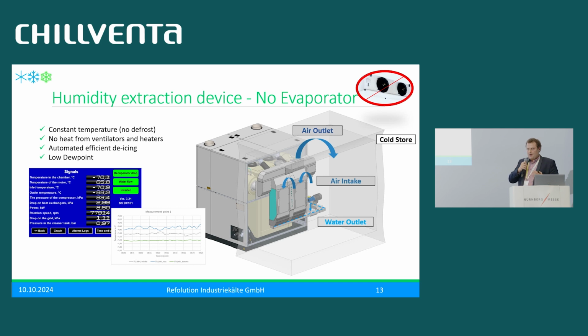And then you ask, but there are ice crystals and at -80 also CO2 crystals, and we have dirt and other things. Yes, and the machine is sucking over 2 filter cartridges. They are obviously redundant, so if one fails, it can suck over the other. And if they are full, they see it over differential pressure. They give a pressure shot against the flow. Yeah, it can still suck here.